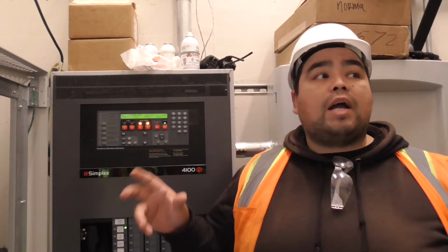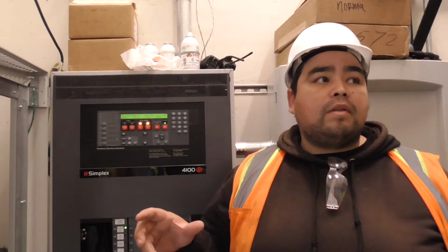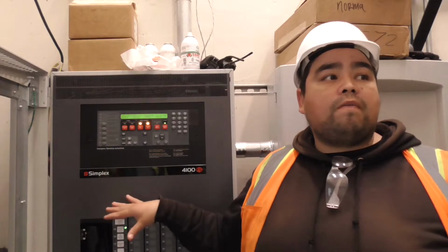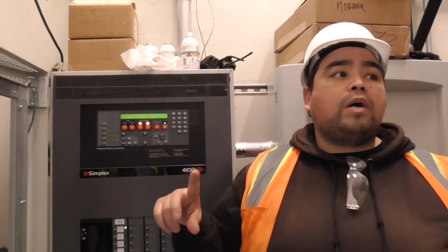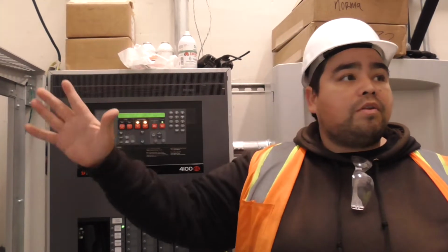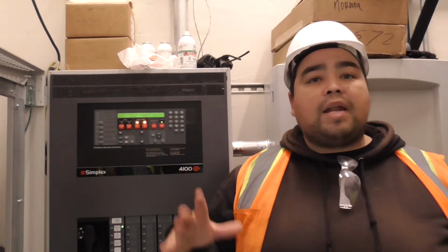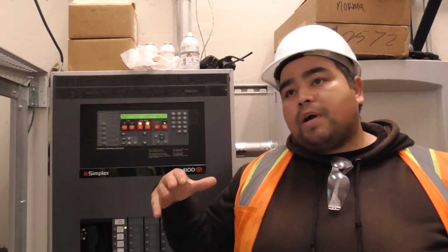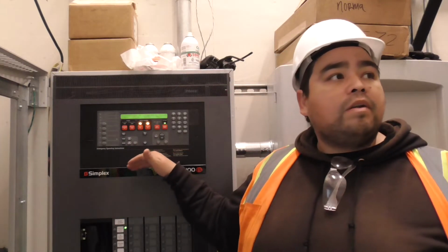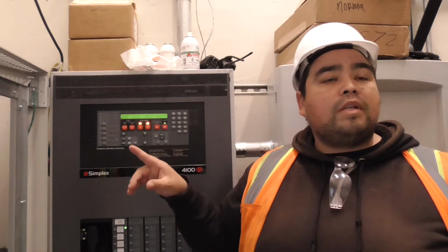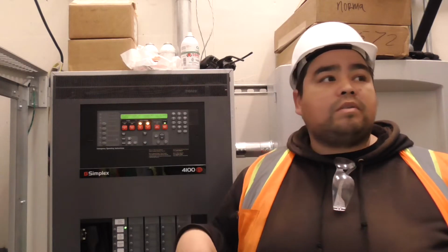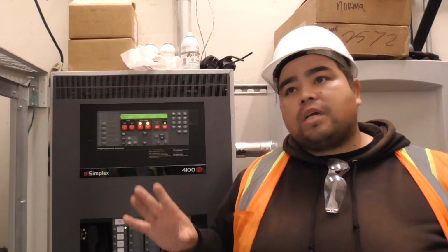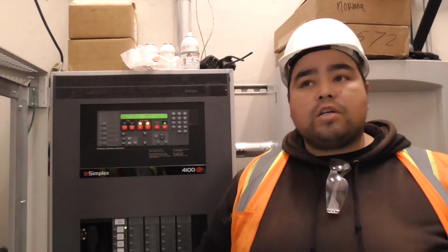Now, they have 2 loops here. I don't know specifically what building you're talking about, but I know there's an old housing loop here. That housing loop is loop 2, so it's not part of this. But anything on loop 1, I can make this communicate with any other. So let's say, for instance, you had a master panel at some residence building. It's possible for me to send a point from here over there to let them know, hey, there's a condition in this building. And that could all be done through programming, as long as it's part of loop 1.